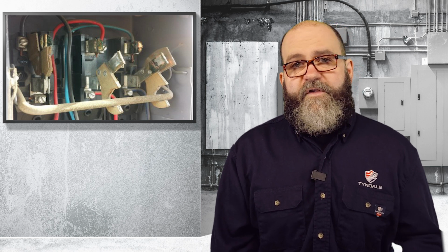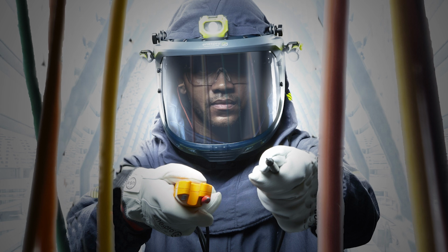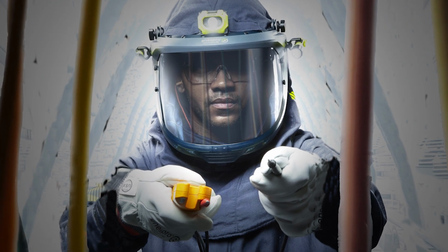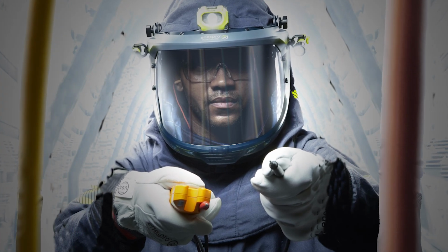It's not always possible to visually verify, so it's also important to understand that to open a disconnect and visually verify will possibly require arc flash and shock PPE. If you can't visually verify, then you need to make sure and follow through with all your testing procedures.